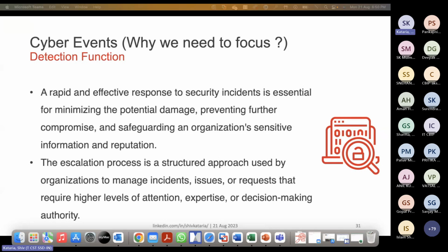So for this, we need to know what could be different options to us, whom should we inform during such events, because the information that is there in the system is very critical to analyze the cause of that particular event. In one of the plants that I have visited, there was one X-ray machine, and this machine was crashing 2 times a week. And the typical assumption is since the machine is running on Windows XP, maybe it is an issue of the OS, and the system is quite old, and the processor is not able to handle the traffic which is there.